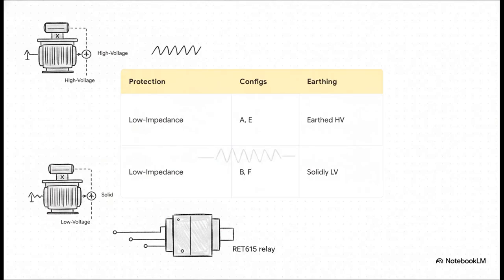Now, what's really interesting about this slide is mapping this directly onto the standard configurations of the RET615 relay. If your application drives you to a low impedance solution, you're going to be looking at configurations A and E for transformers with earthed high voltage neutrals. If you're protecting a solidly earthed low voltage side or an LV side with a neutral earthing resistor, then you'll select configurations B or F.